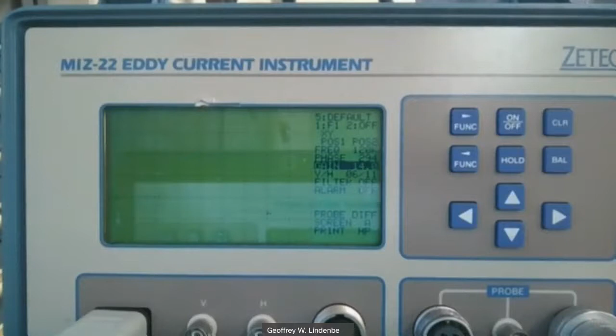You can't just keep increasing the screen because what will happen is you'll oversaturate the probe. This is a fairly small probe, and if my gain's set too high, it's like a speaker that you're sending too much power through, where it starts to clip and all that. On the newer unit, it'll actually tell you if it's doing that. You rebalance. Okay. 1, 2, 3.